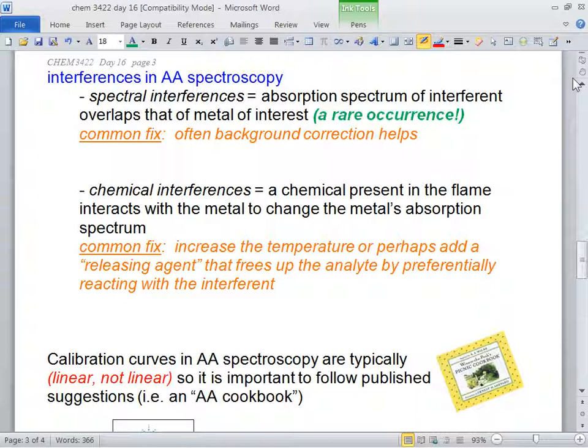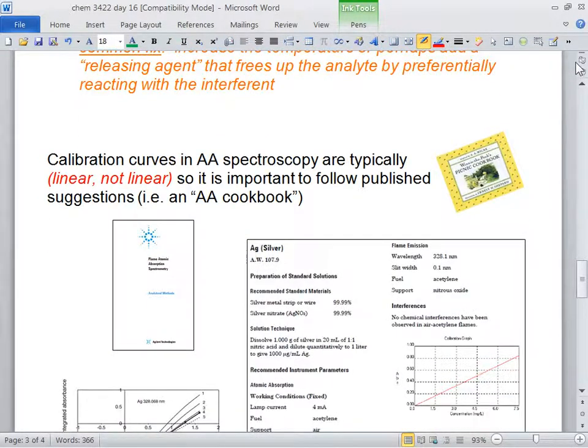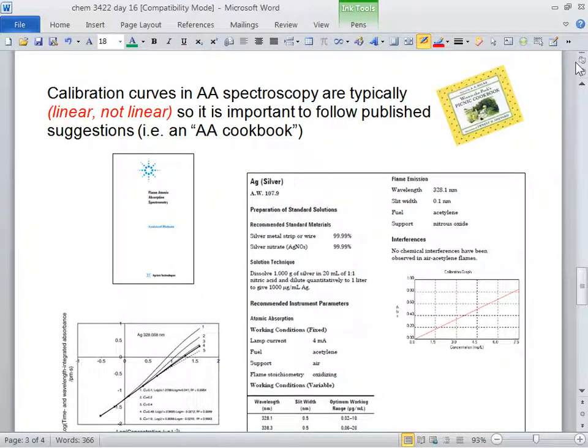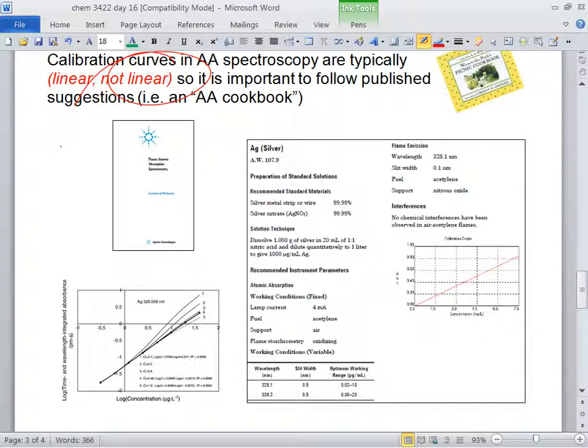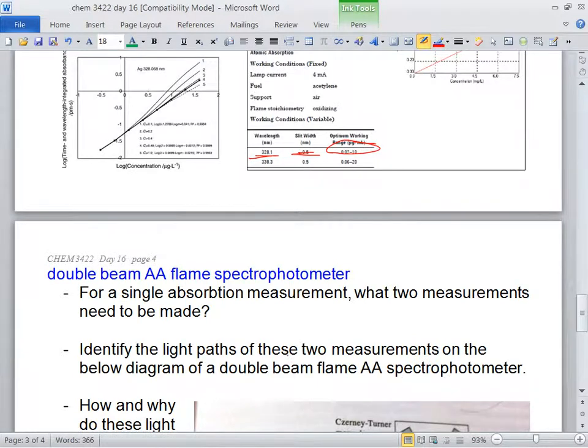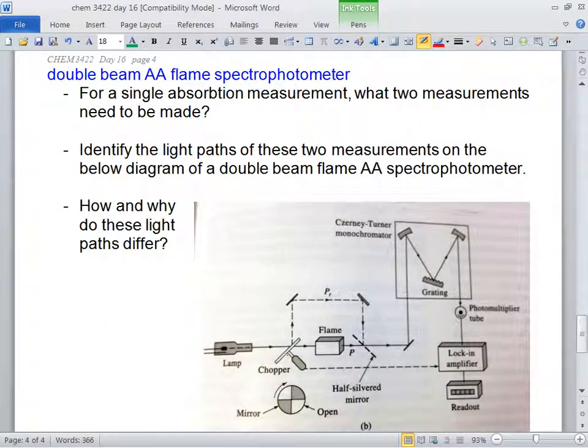Calibration curves. The calibration curves are not linear. That's why you've got to use an AA cookbook. They're not linear. That's why it's so important to use that AA cookbook. Follow all the directions. The slit width, all that kind of stuff. For particular concentration ranges, there's a slit width and there's the line that you should use to get the most linear results.